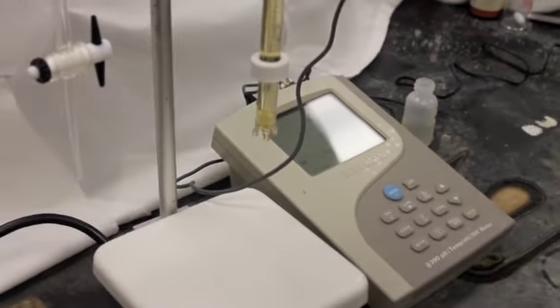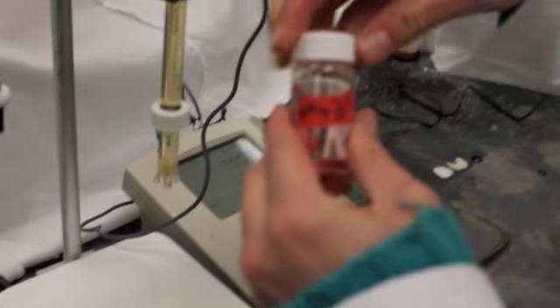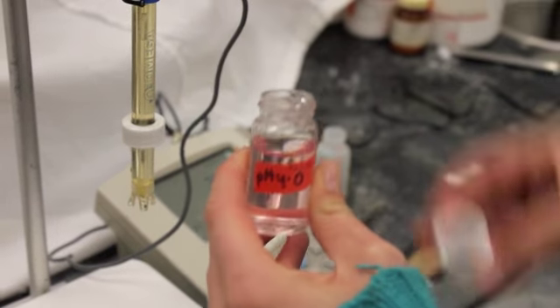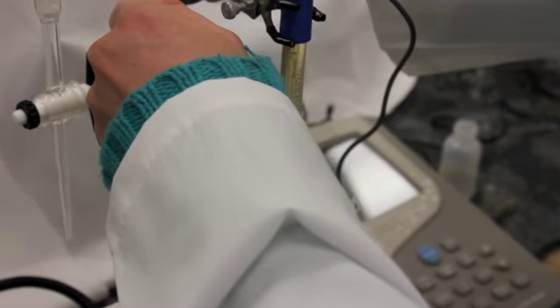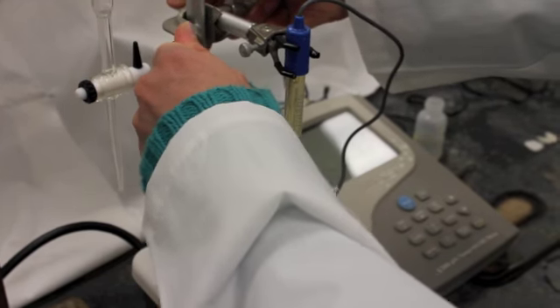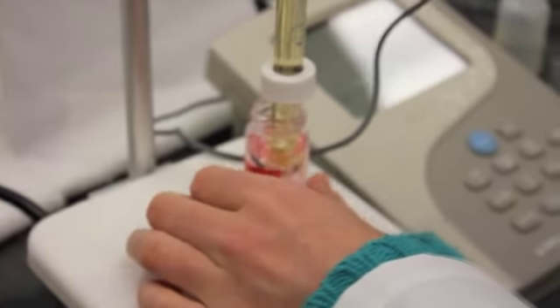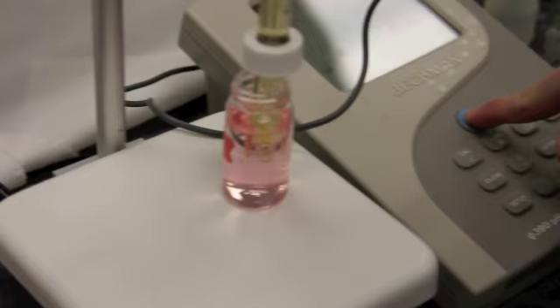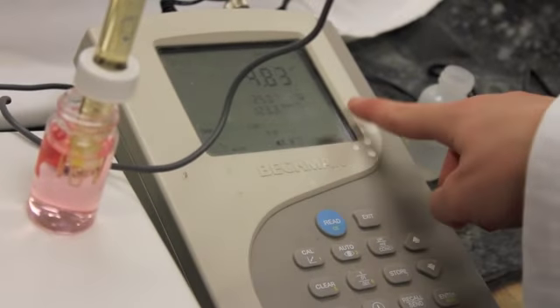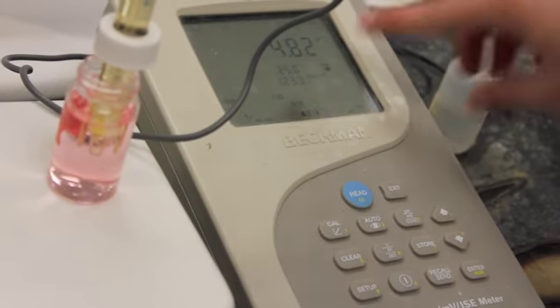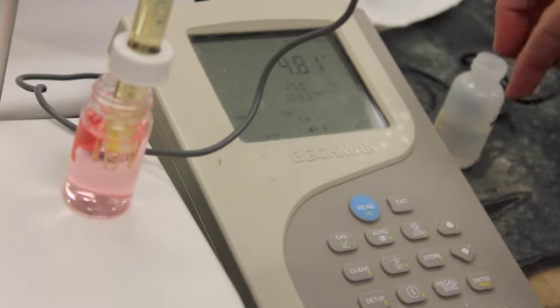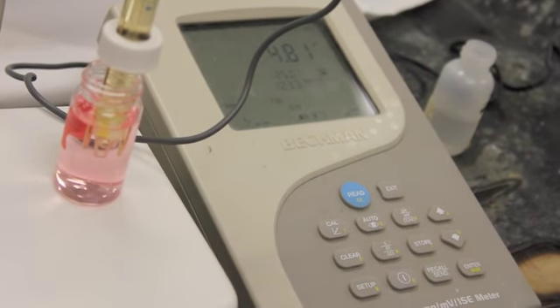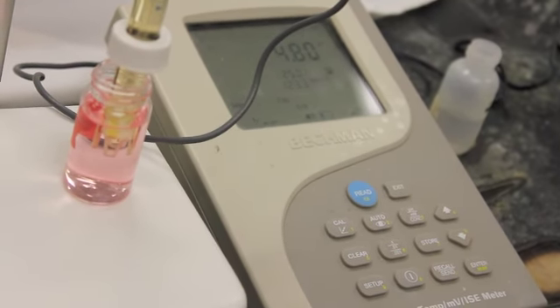And then you take your second reagent, which is the lower reagent, pH 4, and again you immerse the probe into the standard just by gently lowering it down. And again, keeping the probe off the bottom but fully submerged into the liquid. And then again, you just press read. And you wait for the auto eye again to stop flashing. Once it stops flashing, it should be locked at 4 pH, and then your calibration is finished.